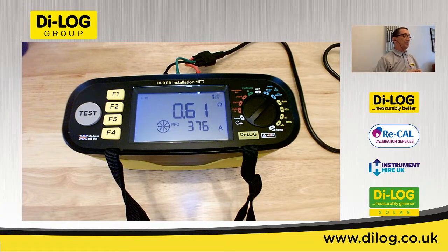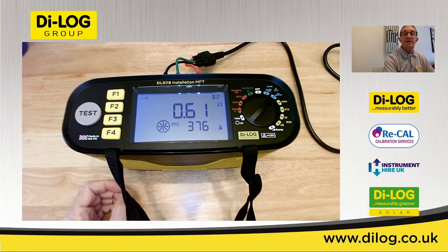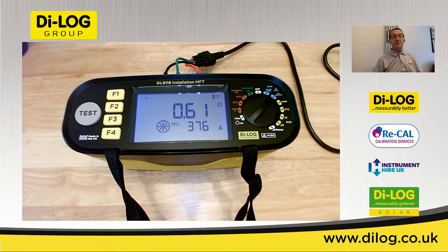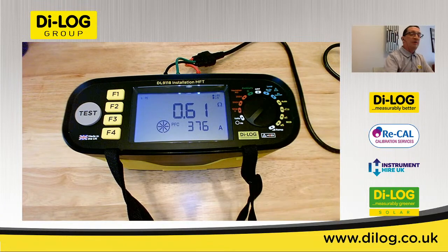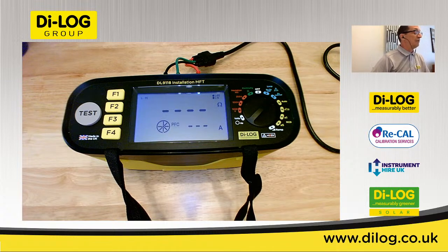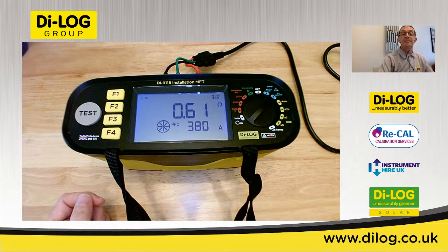Now, lots of different multifunction testers carry out a no trip test in different ways. Ours has unique circuitry in where it will measure a separate loop test, specifically looking for electrical noise or RCD uplift. And that's then recalculated as part of the loop test to give a true and accurate earth loop reading every time. Let's just run that test in process again. So we've got the wheel going round. A couple of rotations of that indicates the test is in process, and round about 8 to 9 seconds later we've now got our earth loop reading.